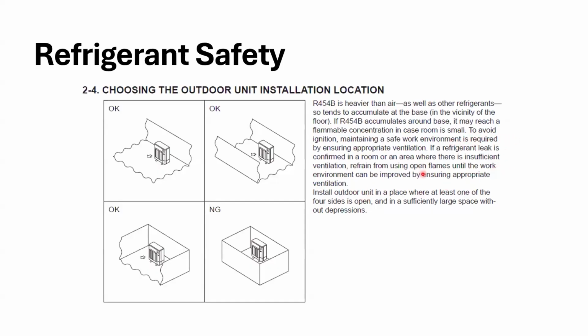So install, I'm just going to skip down here, install the unit in a place where at least one of the four sides is open and sufficient large space without depressions. So again, this is right out of the installation manual for the outdoor units, FYI. So NG, no good, I guess, is what we're getting at there, right? Which would make sense. But so we want to be open, right, on one end or two ends or three ends. So.